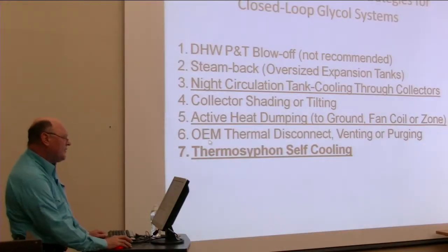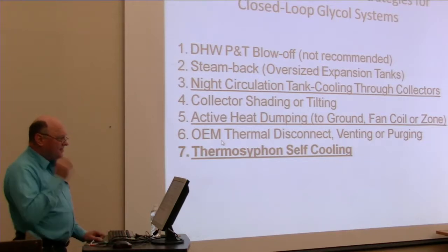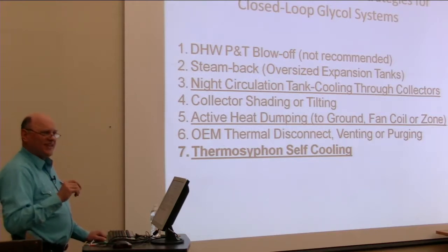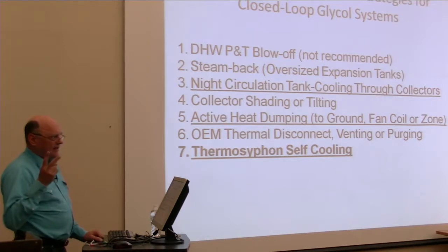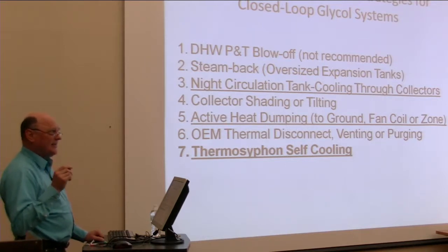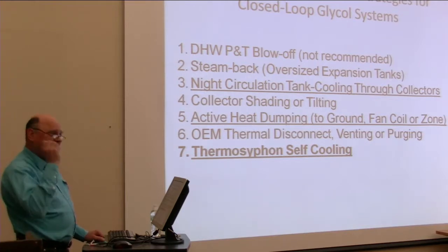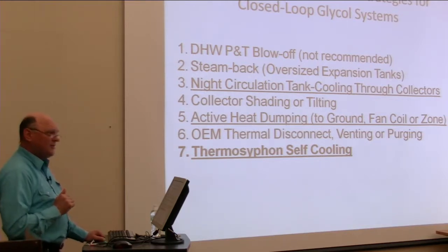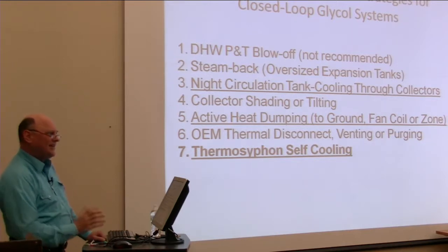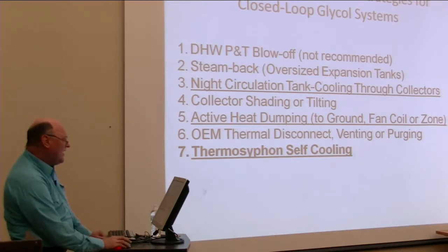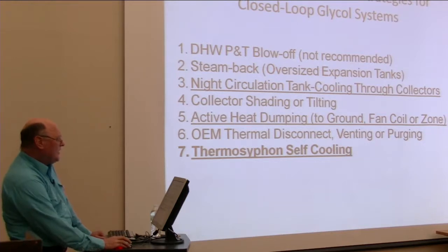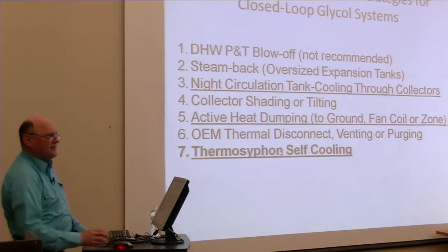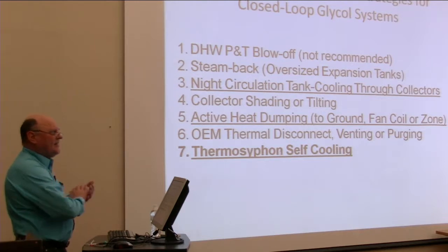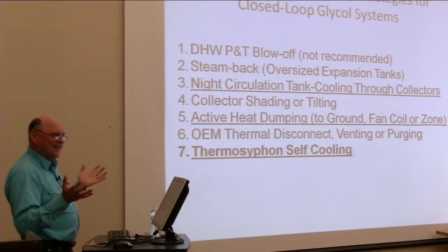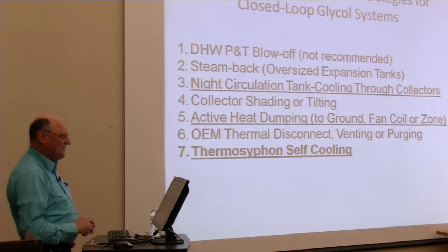OEM means original equipment manufacturers. Some of them build cooling systems into their collectors. There's two collector manufacturers I can think of that actually have what they call thermal disconnects or cooling systems that kick in when the collector gets too hot. These are pretty unusual. You don't find them built into collectors usually. And then the one I like the best is a technology that's been used for many decades, but only a little bit, and we've been resurrecting it because it works so well. It's called thermosiphon self-cooling.